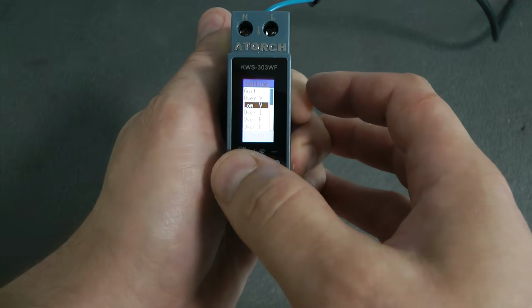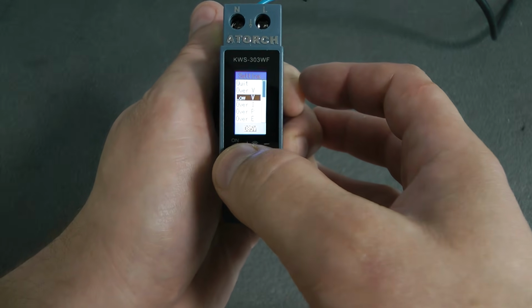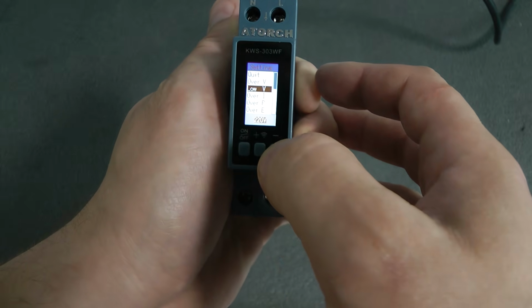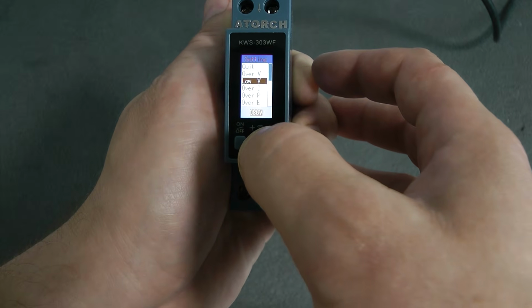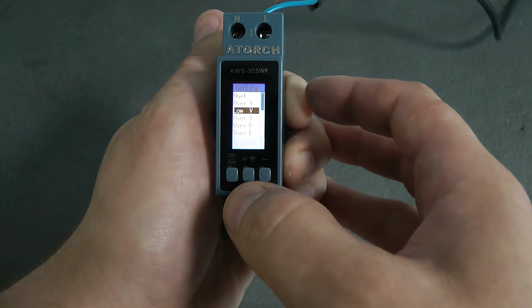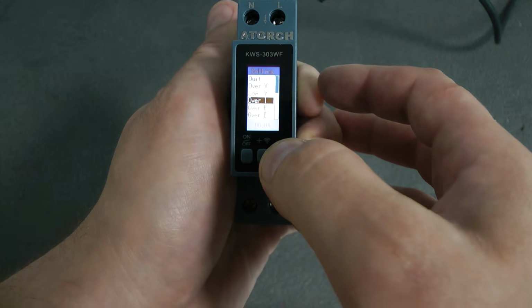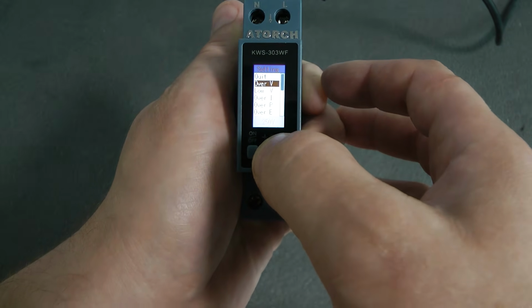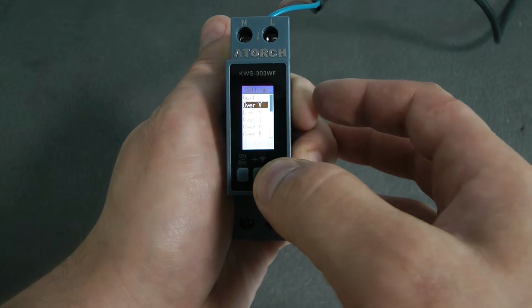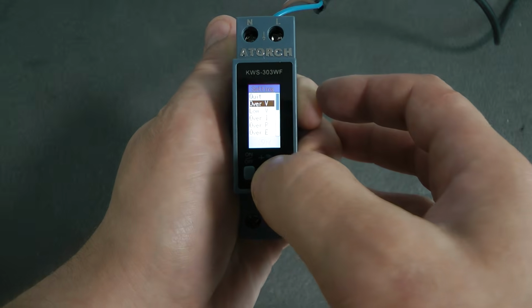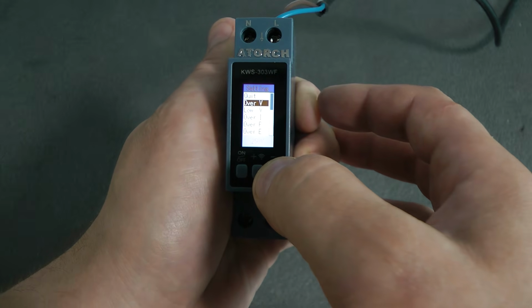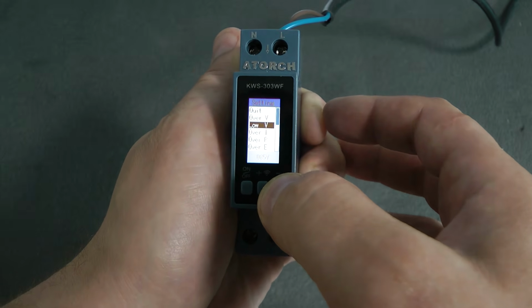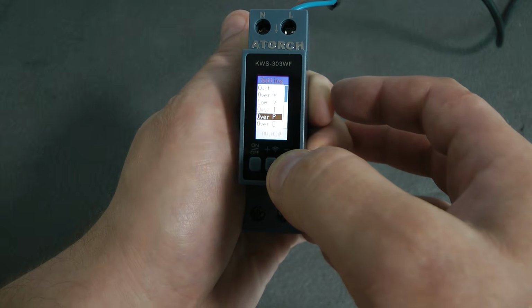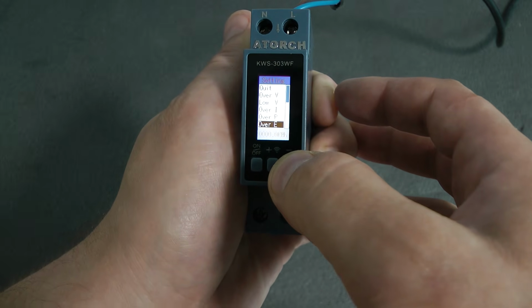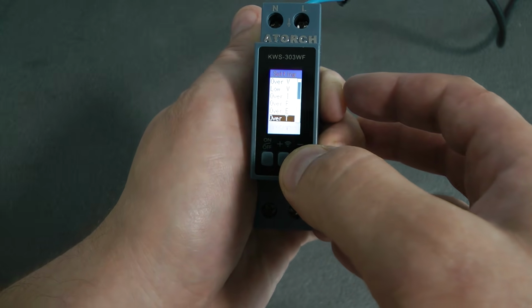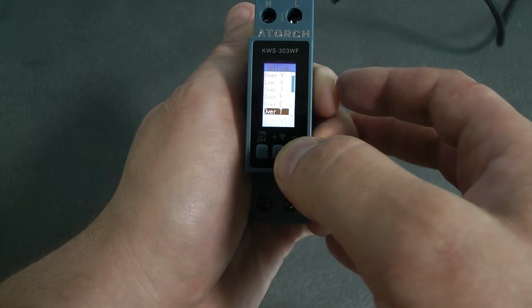To change any value, you need to press the menu button, and then use the plus or minus buttons to change that value. After changing it, press the menu button again and move on to selecting another menu item and changing its value. Here you can set shutdown by upper and lower voltage. By default, the upper threshold is set to 250 volts, and the lower one to 85. The current, power, and consumed energy thresholds are not set by default, meaning they are equal to 0. The temperature threshold is set to 50 degrees Celsius by default.